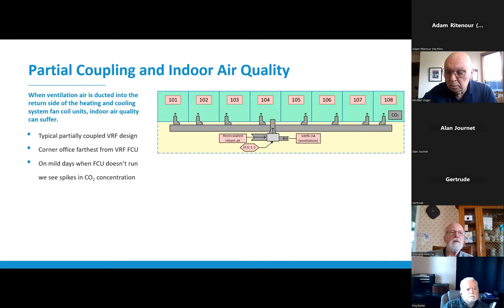Well, what about partial coupling or partial decoupling? So this is a very popular approach, but often it's not done thoughtfully. And what I mean by partial coupling is, if you can see here, when you've got this 100% outdoor air ventilation ducted into the return side of a heating and cooling system fan coil unit, indoor air quality can suffer. So this is a partially coupled system because you have this ventilation air coming in on this backside of this fan coil unit. So this is exactly what's happening on one of our systems that we've been monitoring.